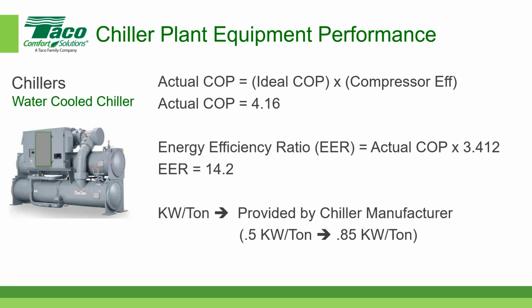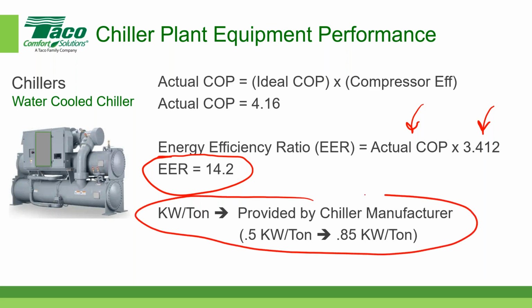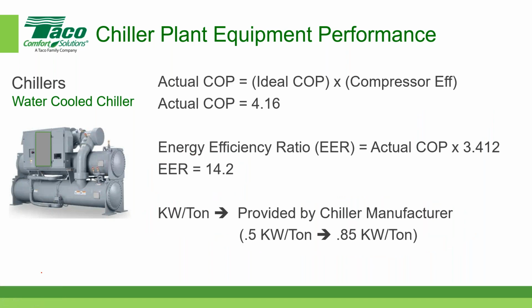Okay. We talked about the actual COP. One of these other weird values in the American system is called the energy efficiency ratio, or EER. If you take the actual COP times this value here, 3.412, you remember that one, the EER, the energy efficiency ratio, is 14.2. And the kW per ton is provided by the chiller manufacturer. You and I cannot come up with a number for the kW per ton, for example at peak load. You would get that from the chiller manufacturer, and I said that would be in a range. That's a fairly common value. You can get them that are lower, and you can get them that are higher. All right, we talked about that.